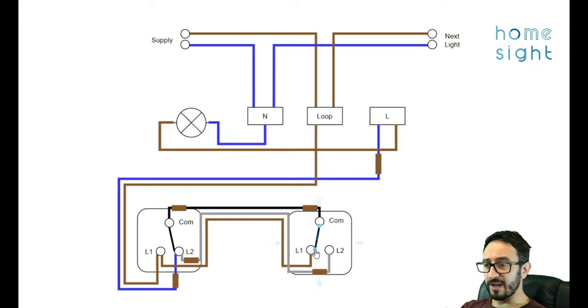Now obviously we can break that circuit by switching this one over to here or equally we could have switched this one back across as well. So now they're both in the same state both on L2 that will be off. Now if I were to switch this one onto L1 our electricity is going to come down our brown wire to L1 up to our common across to our common onto our L2 onto this grey wire which comes onto our L2 here and ultimately onto our blue wire which is going to complete that circuit along here up to our bulb.